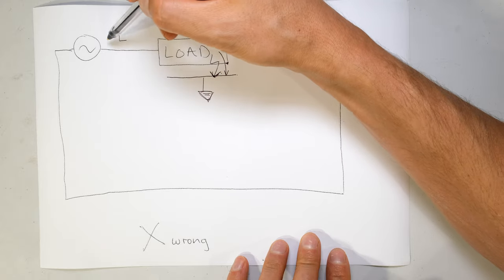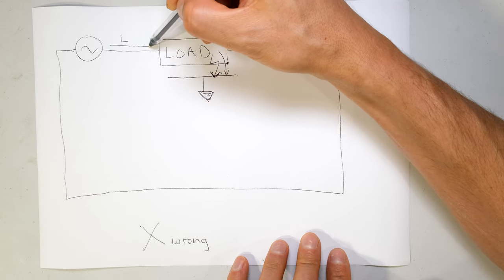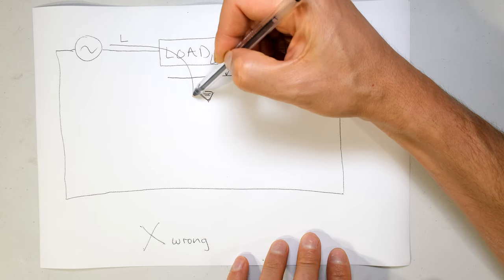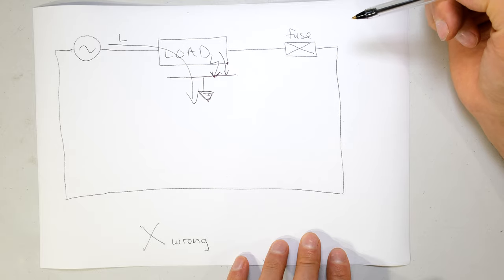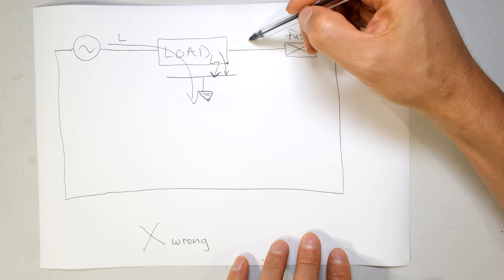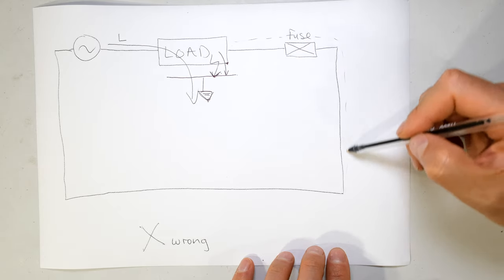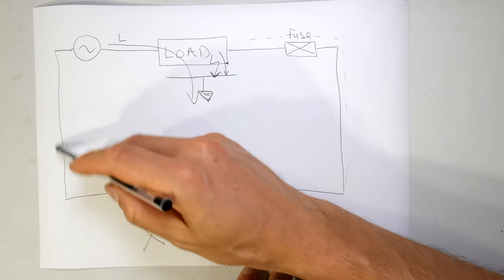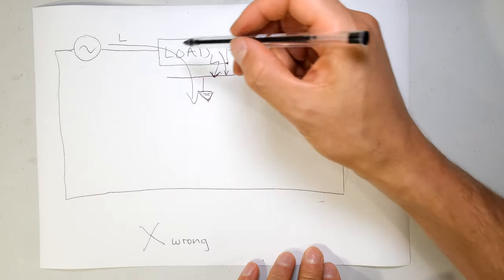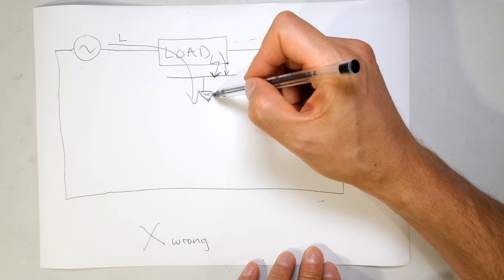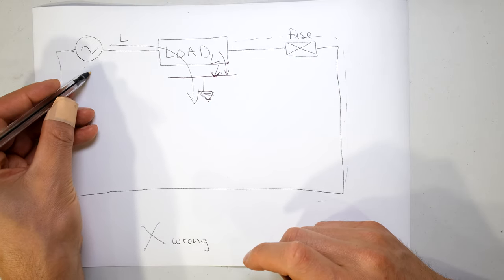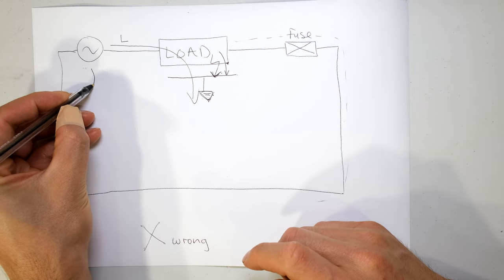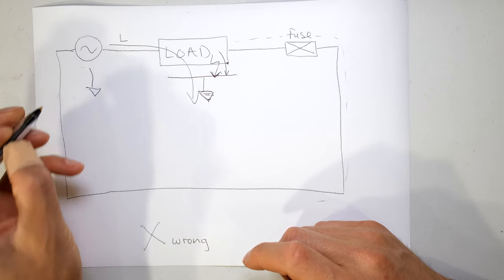So what happens is the current is going to flow like this. It's not going to flow in this direction. It's not going to go via the neutral all the way back to the supply. It's going to flow directly into earth. Why? Because don't forget that the supply is also with reference to an earth point.